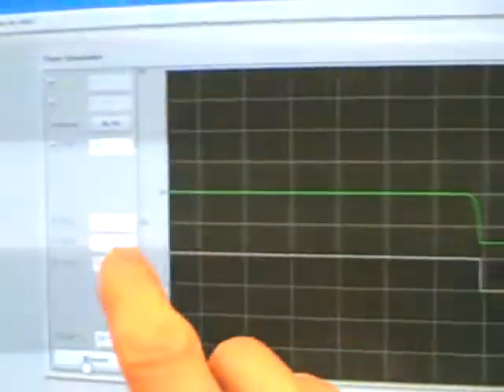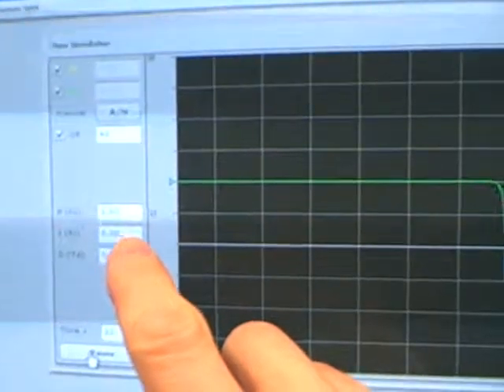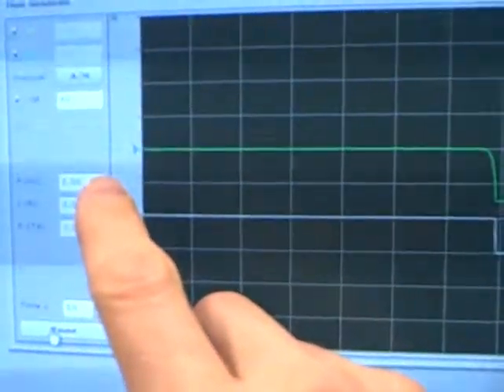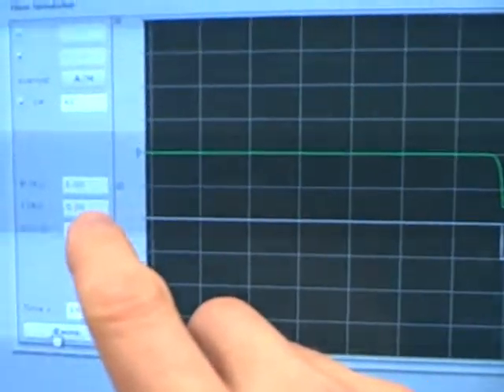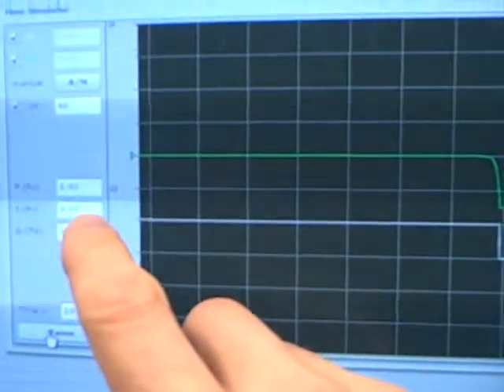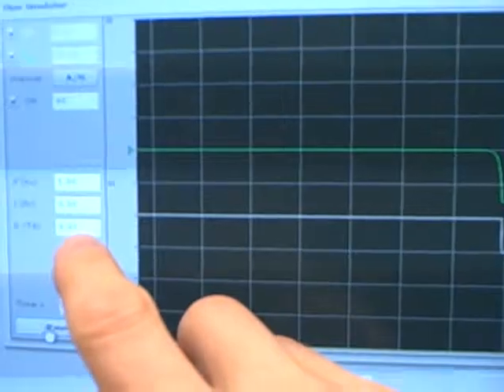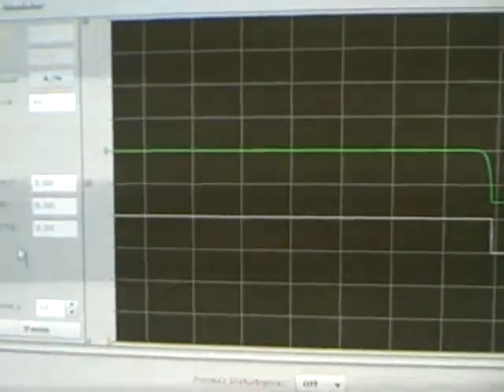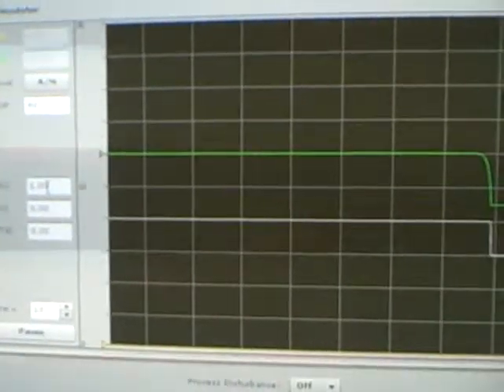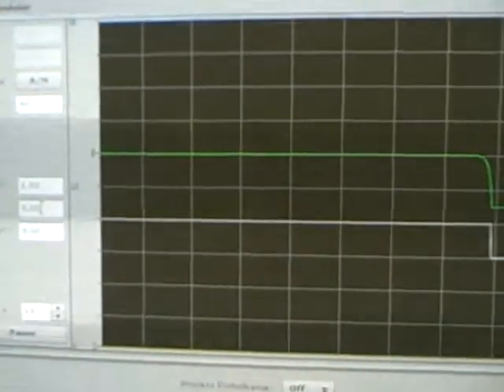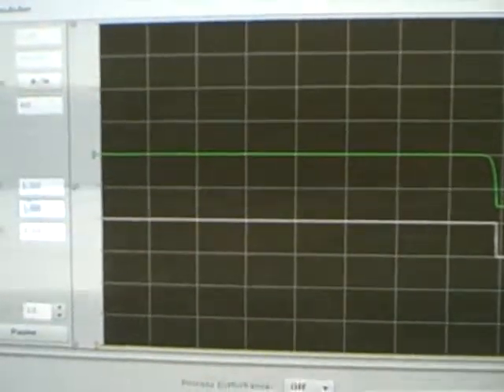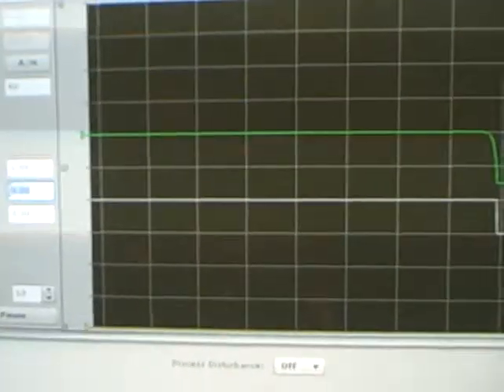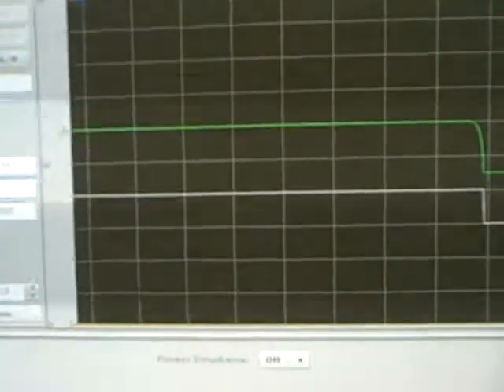If I look at my tuning parameters here, the default tuning parameters at gain of 1, 0 repeats per minute for integral, and 0 minutes for derivative. What I'm going to do is keep the gain at 1, and I'm going to change this to 1 repeat per minute on my integral. I'll enter that value.